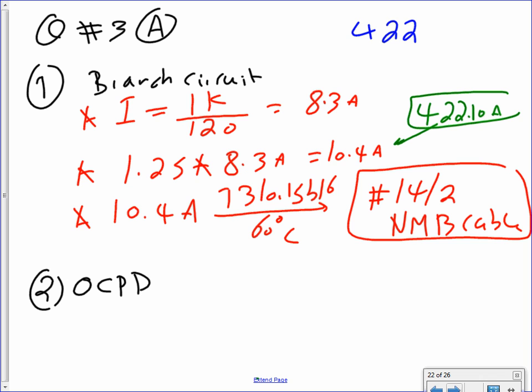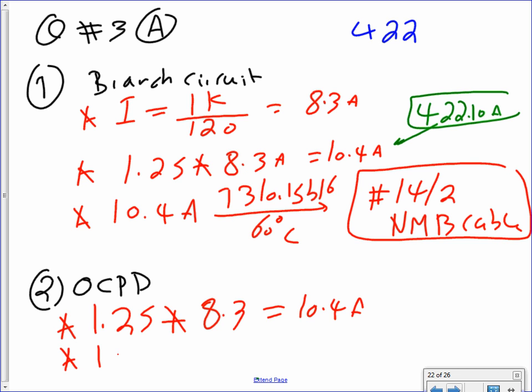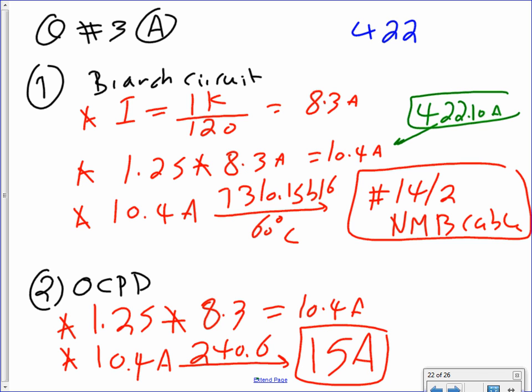For the overcurrent protection device, guys, the same thing I would do is continuous load 1.25, even though it's a motor. You have the horsepower, you could go higher than that, but 1.25 continuous load with overload multiplied by 8.3. That'll get you 10.4 amps. Then you take the 10.4 amps, take this one to 240.6. That will get you a healthy 15 amp single pole circuit breaker.